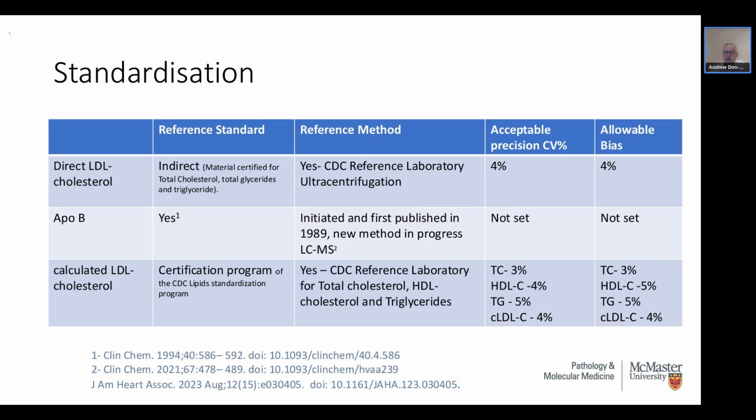And so it's not really a direct measurement, it's an indirect measurement, but it is quite a well-maintained method. It is a reference method, and it has been in place for a good number of years. And so it comes up as a pretty good reference method with an indirect reference standard. There's acceptable precision targets of 4%, and allowable bias is 4% as well.